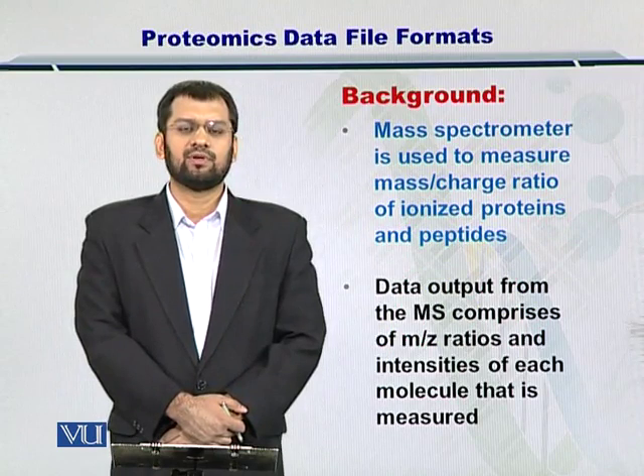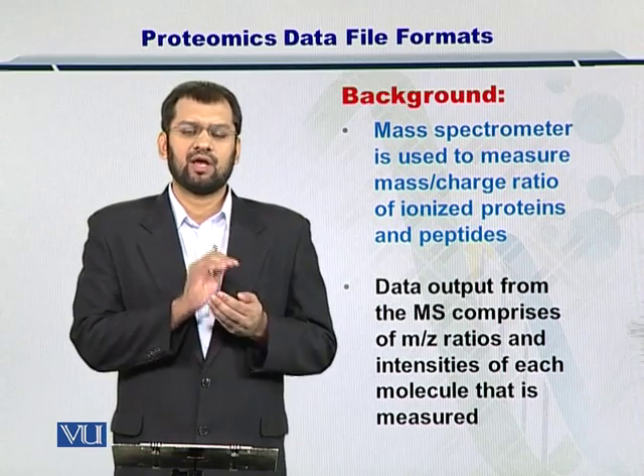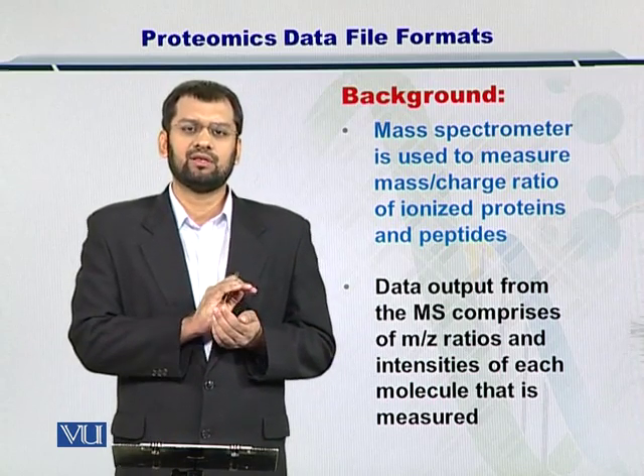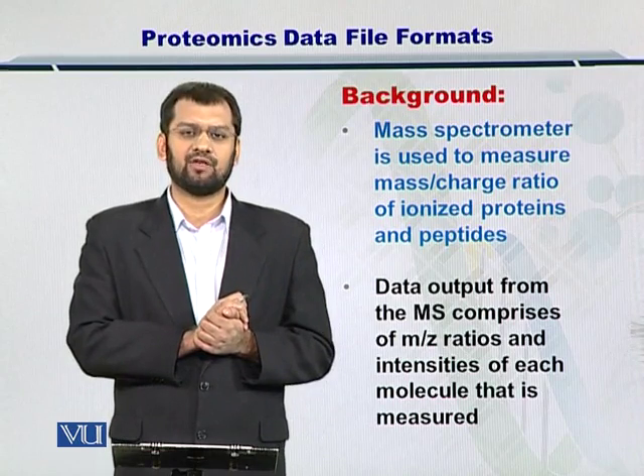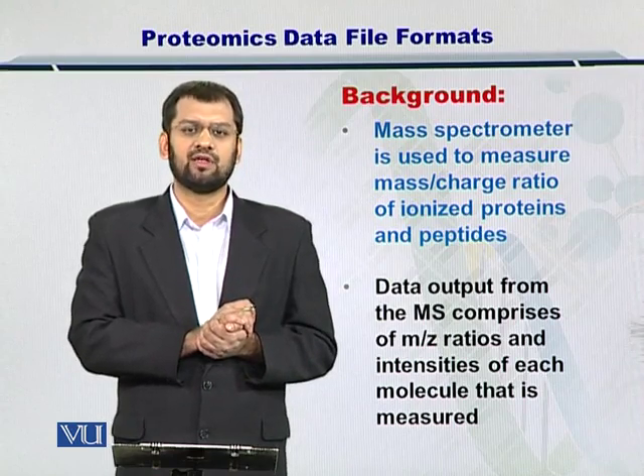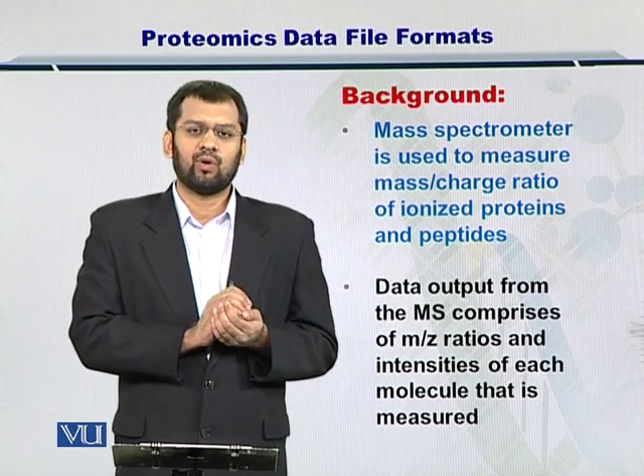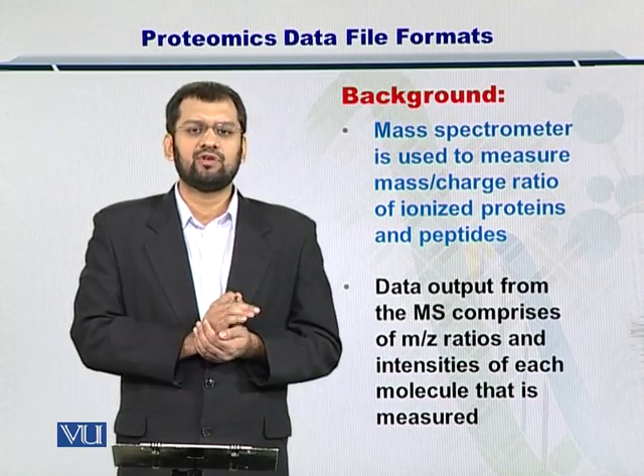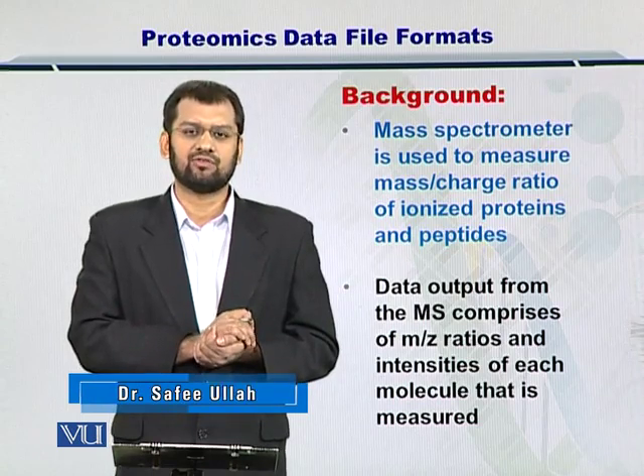A mass spectrometer is used to measure the mass over charge ratios of proteins or peptides. Once you ionize a protein or a peptide and inject it into the chamber of a mass spectrometer, it gets deflected according to its mass by the very big magnetic field. These deflections are measured as electrical signals representing the strength and magnitude of the signal, which then needs to be translated into the mass over charge ratio. This ratio can then be written in the form of a file on a computer attached to the mass spectrometer.